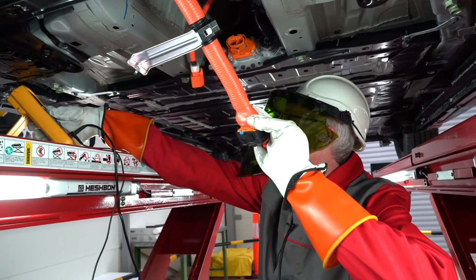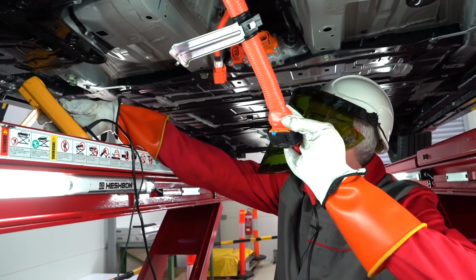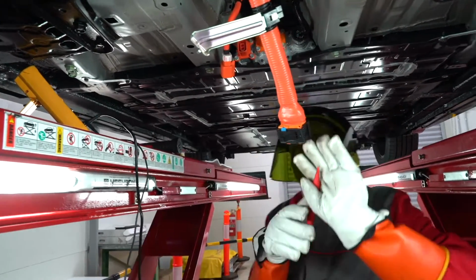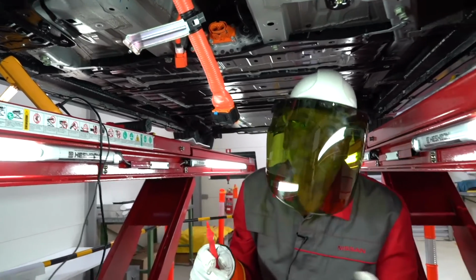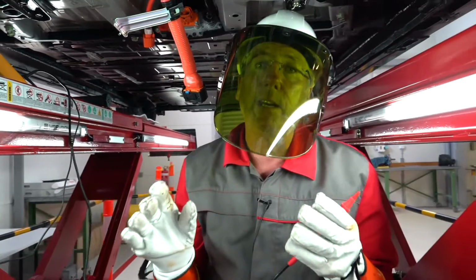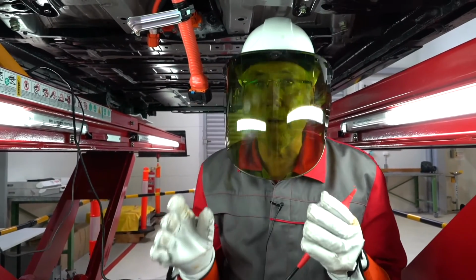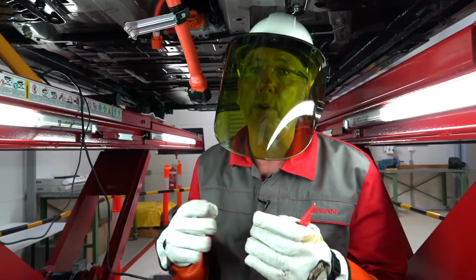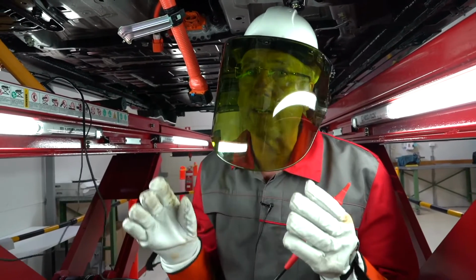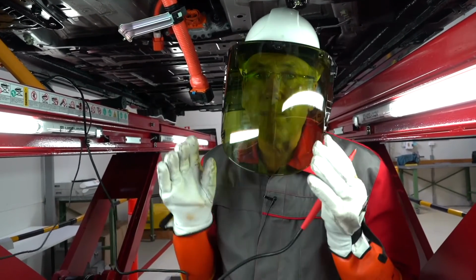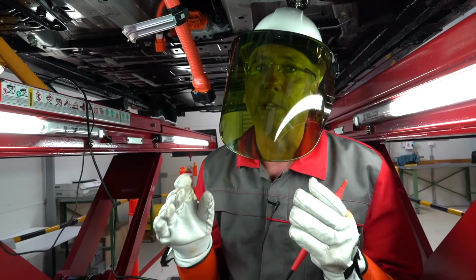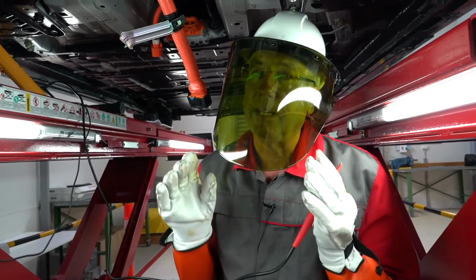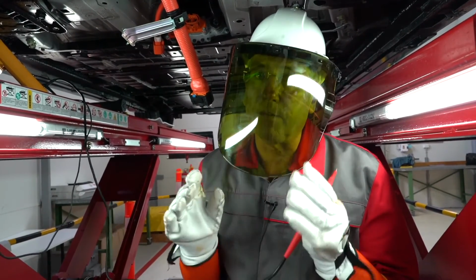settling and stabilising, and this one of course is a brand new car, it's beautiful. So that is an insulation resistance test. Once again, it depends upon what component you are doing a high voltage repair on. Please though, all of the insulation resistance tests must be done totally safely. It is the real deal. PPE and safety first, please.